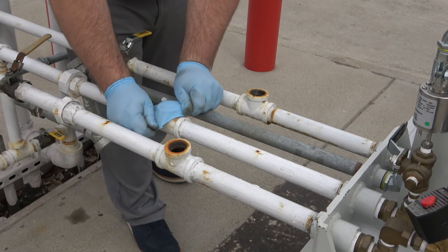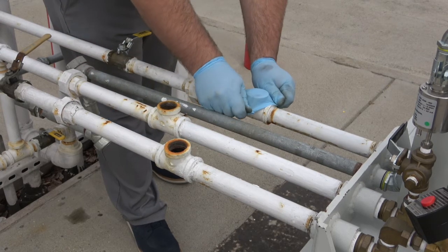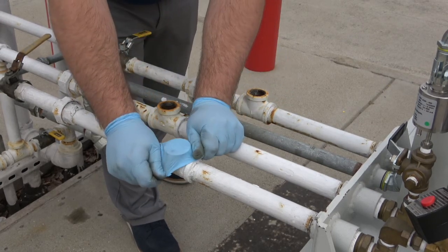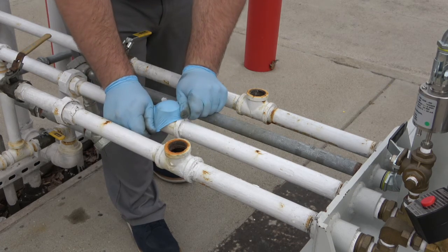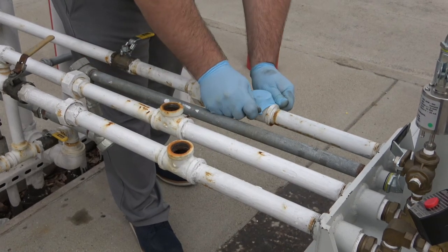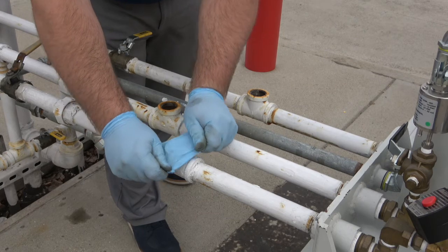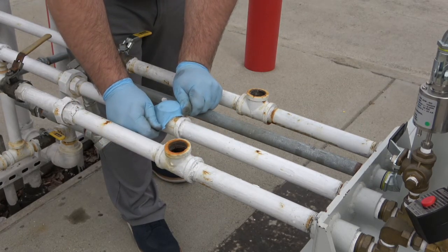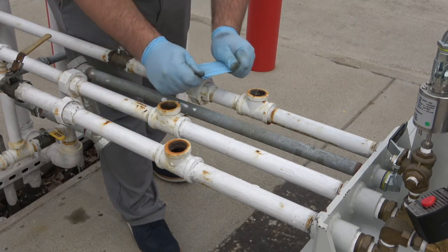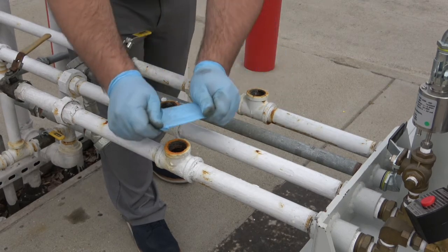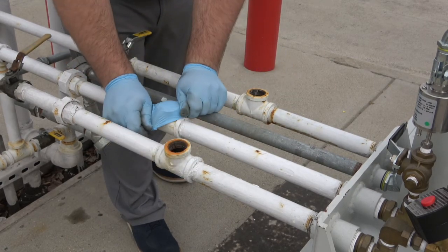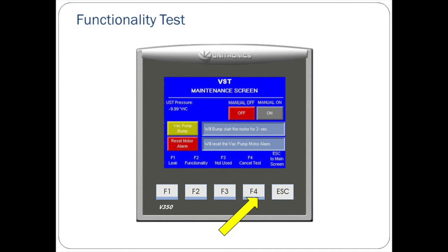During the purge mode, place your hand over each open T-fitting. You should feel the following: no blowing or suction at the vapor inlet T, no blowing or suction from the air outlet, and air blowing from the vapor return. Again, if there is suction or air blowing from anywhere unexpected, refer to the troubleshooting section of the Green Machine manual in Chapter 8. Once you have confirmed these airflows, the functionality test is complete.